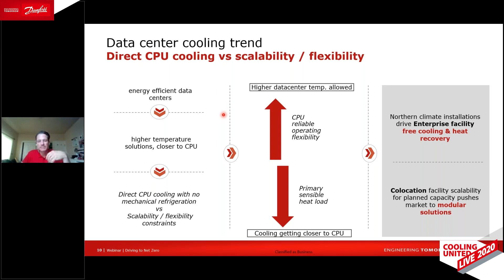You already see this happening in some new data centers being created in Denmark and Sweden, for example. What they're doing, or what we see as the biggest opportunity, is capturing the heat rejection—Kevin touched on this briefly earlier. When capturing that heat rejection, it's much better to tie it to a district energy system so you can fully utilize that heat, because it's higher capacity than the cooling system itself. I'll come back to that.